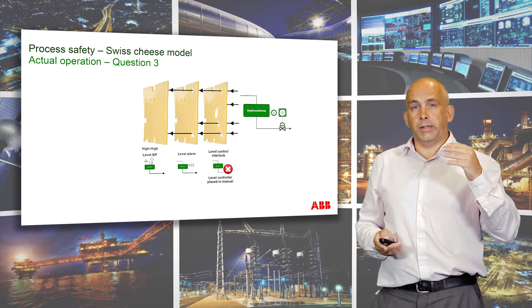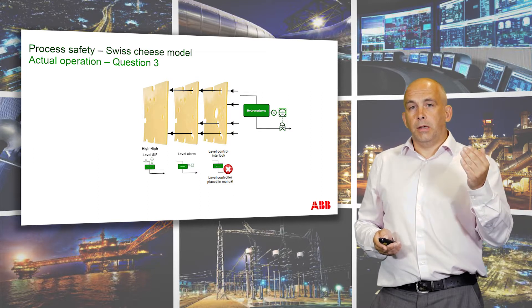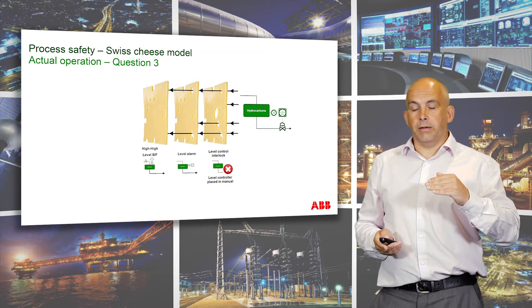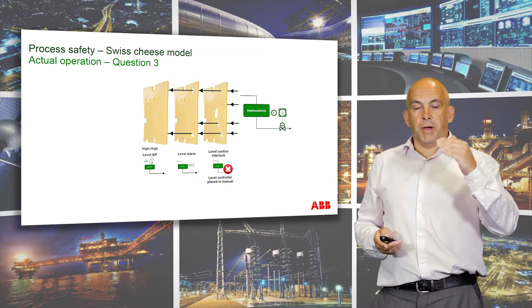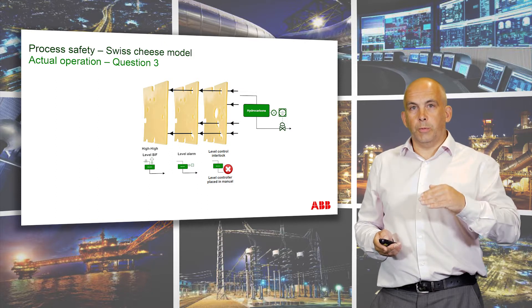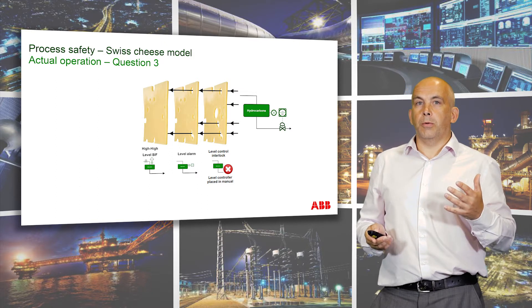The alarm annunciates, the operator accepts it, then the level goes back down again. The alarm activates again, the operator accepts it, it goes back down again. It becomes annoying for the operator, so he decides to mask that alarm until the level control gets resolved. As soon as the operator masks that alarm, we've made the second barrier ineffective — introducing another hole in that particular slice of cheese.